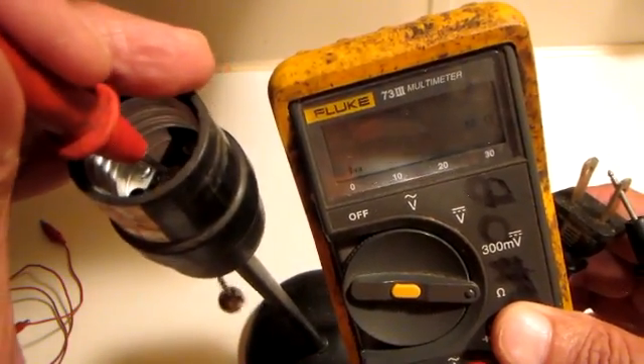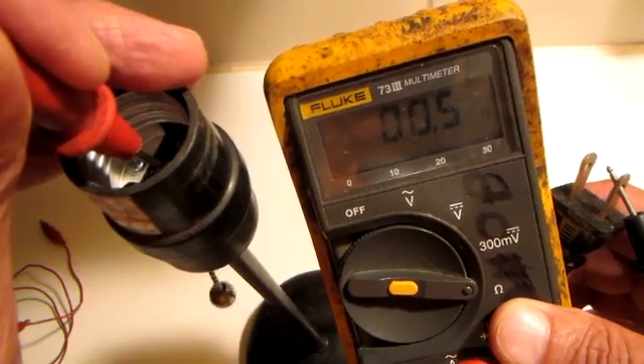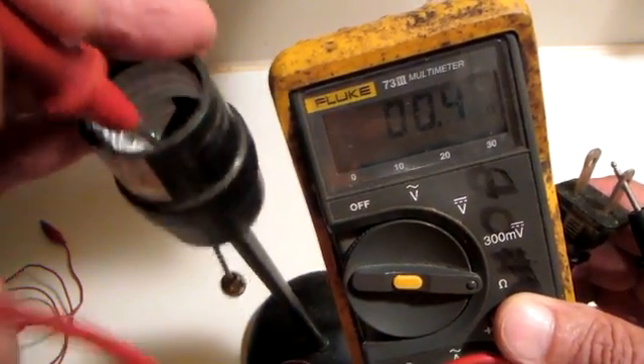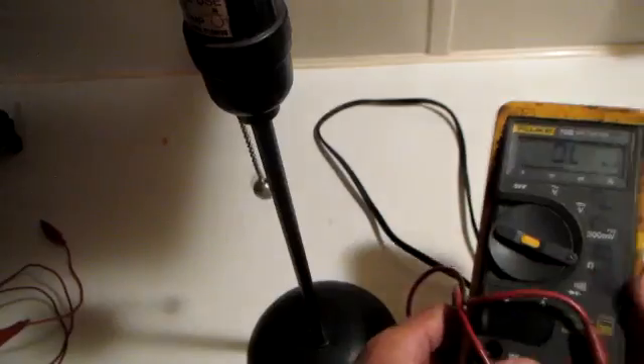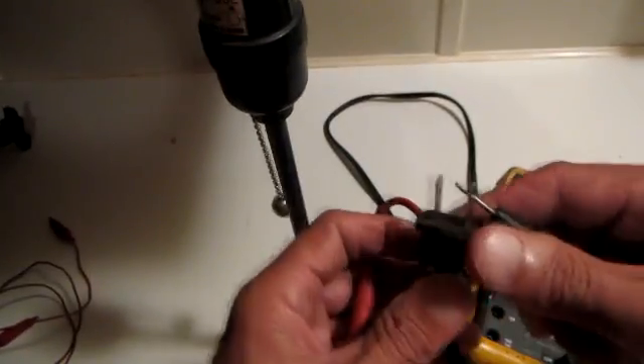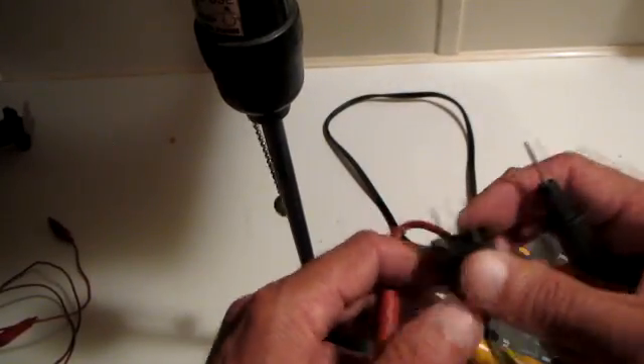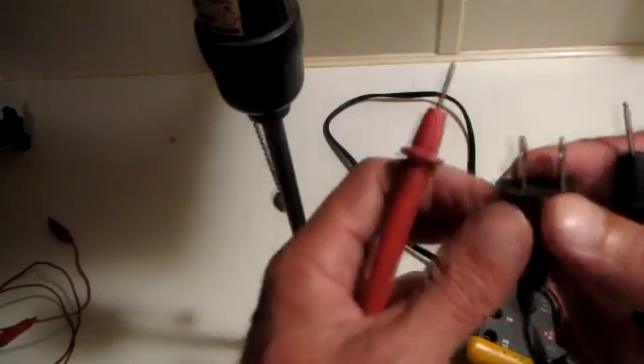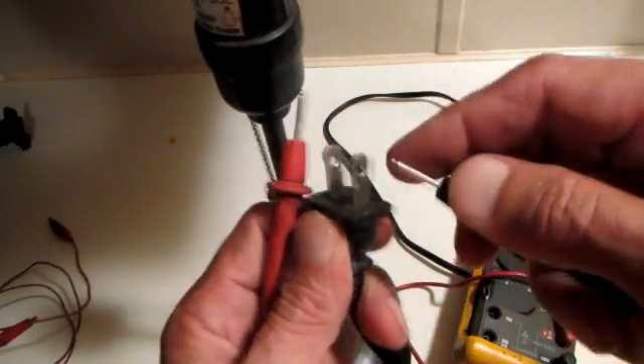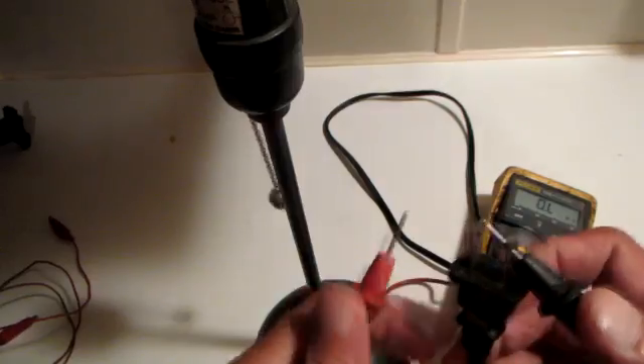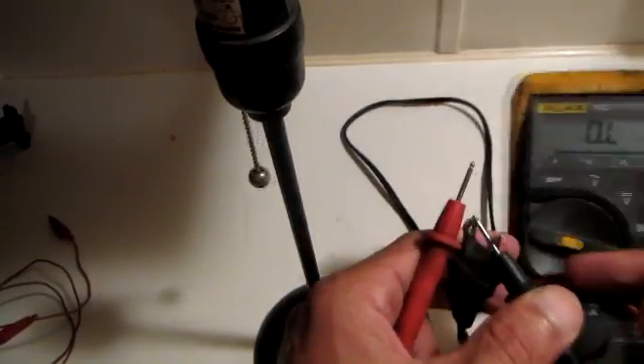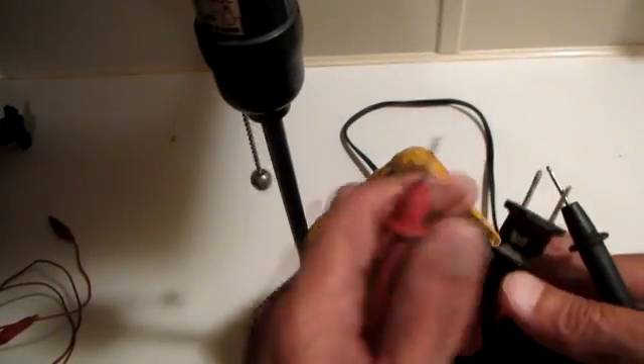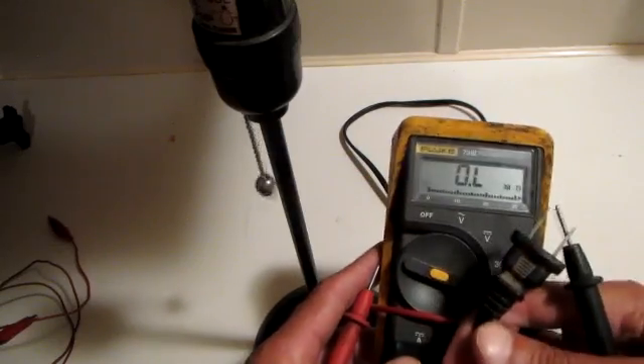This socket is wired properly to the plug, so we verified that's all good. Also you might want to touch the ground threads to make sure you have a dead open while you're doing that test. Make sure your hot wire isn't shorted to the ground contact at the socket.